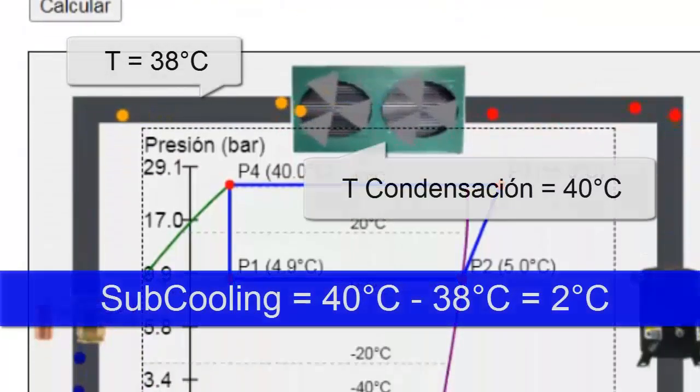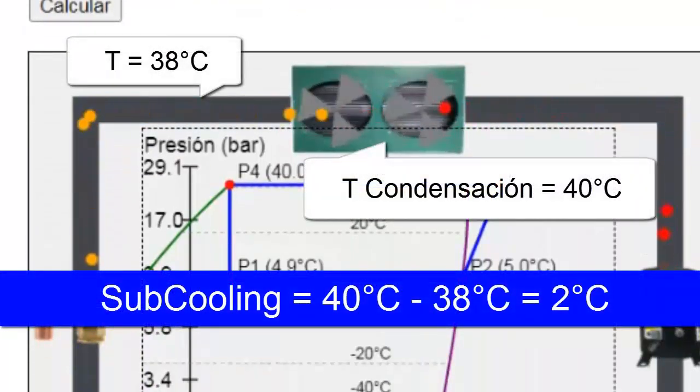Subcooling is the decrease in refrigerant temperature when it is in liquid phase at the condenser outlet, improving system efficiency. For example, if the outer surface of the condenser is clean and has adequate airflow, slightly higher subcooling values can be achieved.